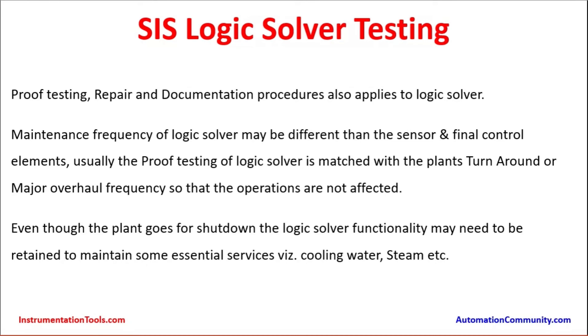Logic solver testing: proof testing, repair, and documentation procedures also apply to logic solver maintenance. The frequency of logic solver testing may differ from that of sensors and final elements. Usually the proof testing of the logic solver is matched with the plant's turnaround or major overhaul frequency so that operations are not affected, because the logic solver is the heart of the Safety Instrumented System. Even during shutdown, some valves and instruments may need to be stroke-tested. The logic solver application is quite critical — even when the plant shuts down, the logic solver may need to maintain essential services like cooling water and steam.